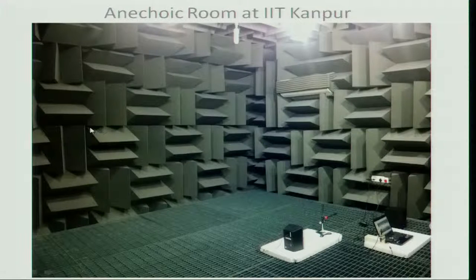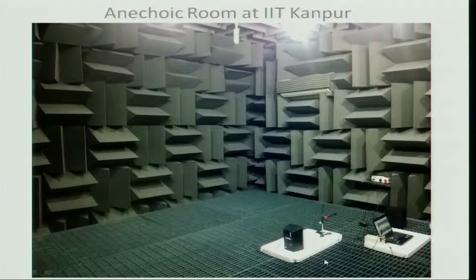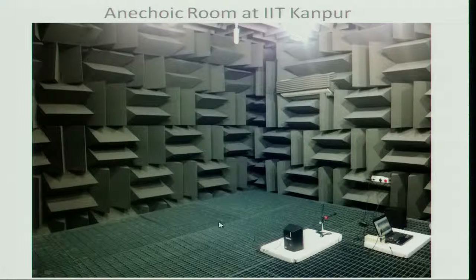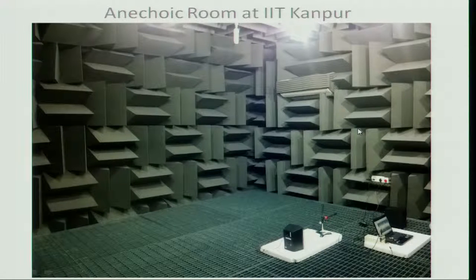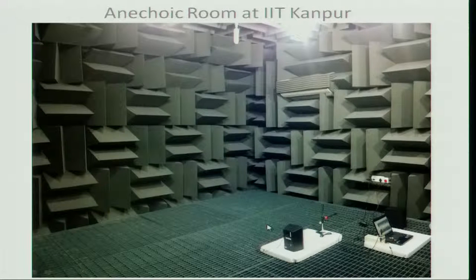This is the picture of an anechoic room which we have at IIT Kanpur. It shows a porous surface on which you can stand, and below this surface there is a strong grill. Below the grill there are also cones made of foam, and these foam cones are also present on the top surface. All six surfaces have these types of cones.